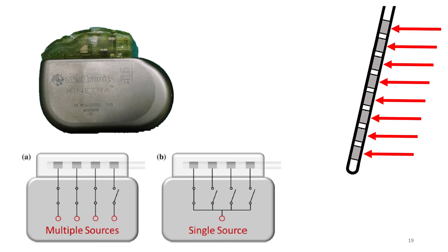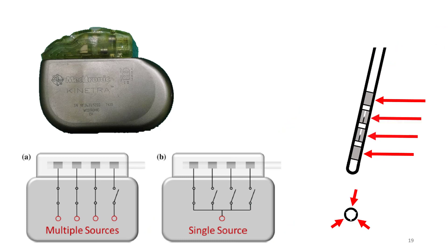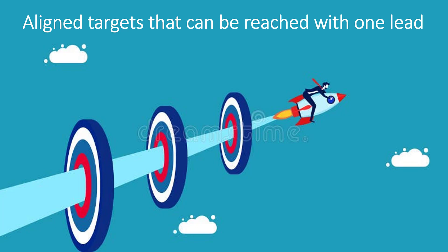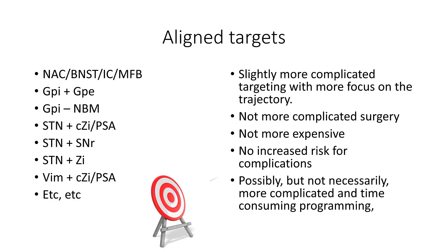However, we have lately also seen the development of hardware which should be beneficial regarding multiple targets, such as multiple source IPGs with individual control of the contacts, as well as electrodes with more contacts and directional steering of the current. Looking at the current situation regarding multiple targets in DBS, it is important to differentiate between targets that can be reached with one single electrode and those necessitating multiple electrodes. We have quite a few of these aligned targets — some only suggested, others commonly used. With aligned targets, the targeting becomes slightly more complicated with more focus on trajectory, but the surgery is not more complicated or more expensive, and there should not be an increased risk for complications.